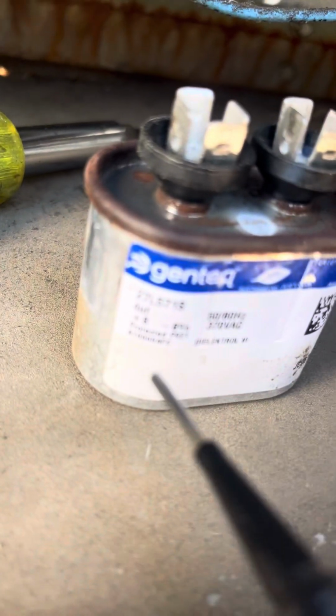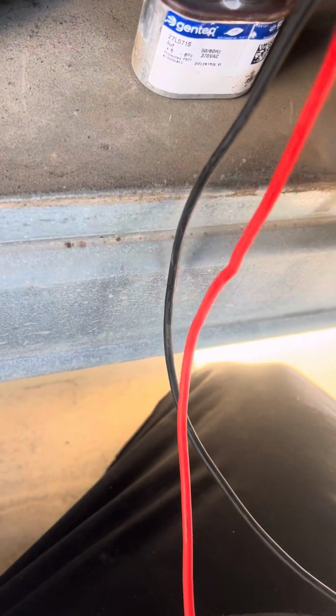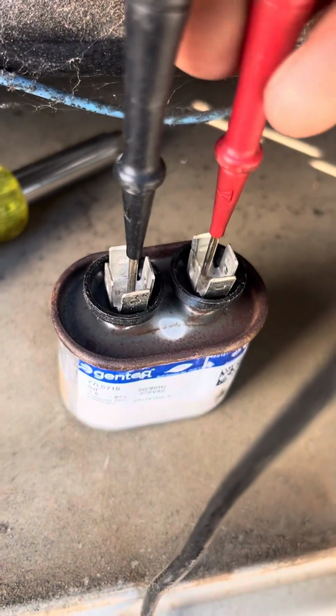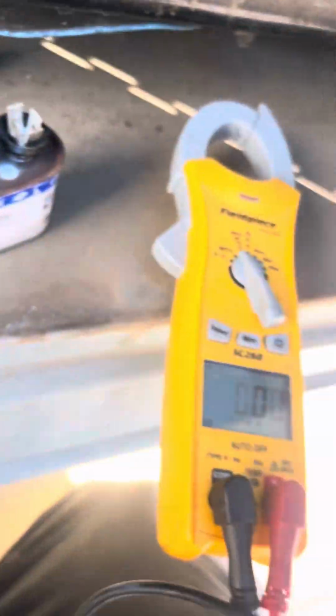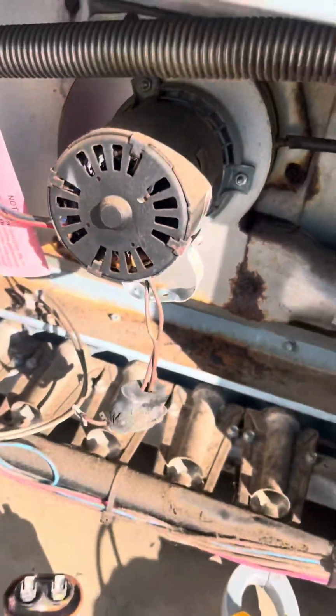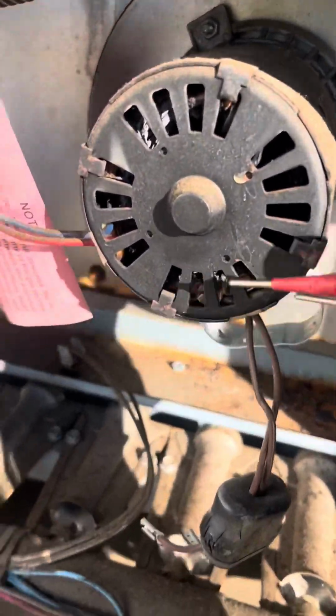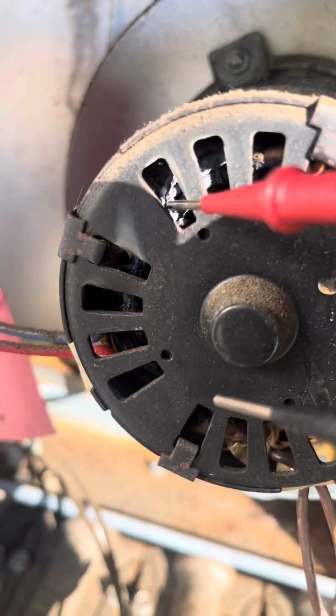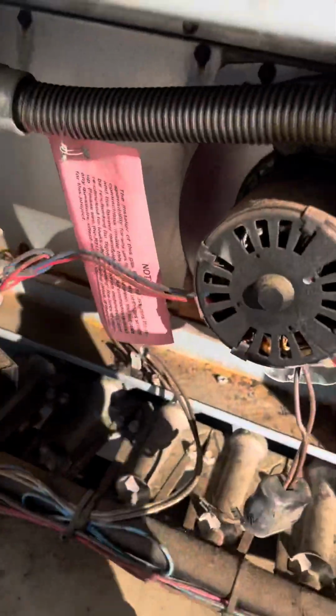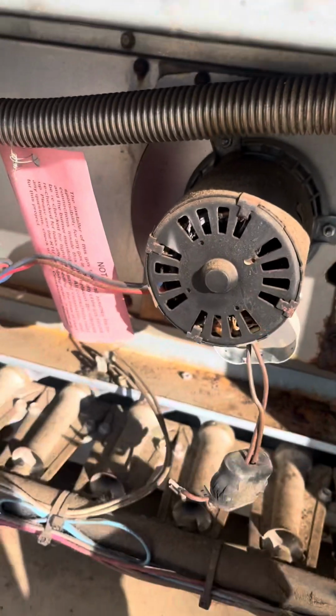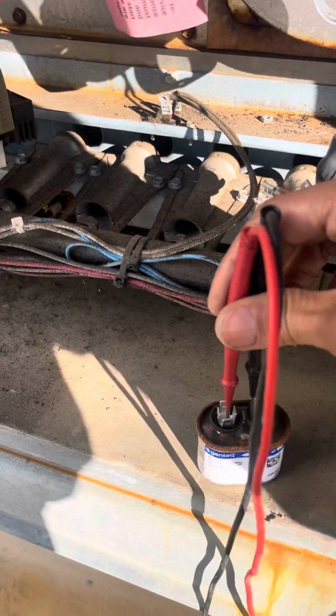But that say 4 UF, that just means microfarad. I'm gonna check that for y'all right quick, show y'all, cause it can easily just be a bad capacitor. I'm on these terminals, good. We read OL. She shot, man, all the way. She through. So we gonna get that motor out of here. We gonna come with a capacitor. These Fasco motors. The capacitor from this one that I said is obviously grounded. I ain't got no power on, so don't do what I do unless you did what I did. You know? Don't let that go over your head.